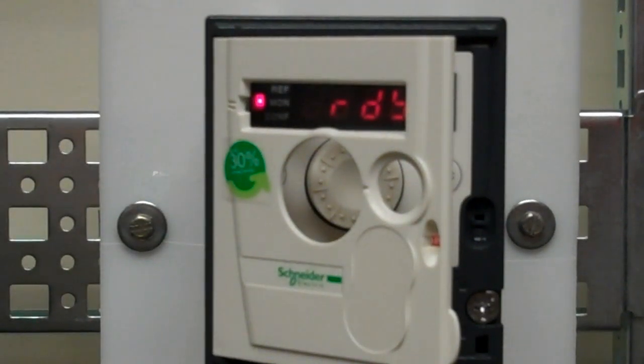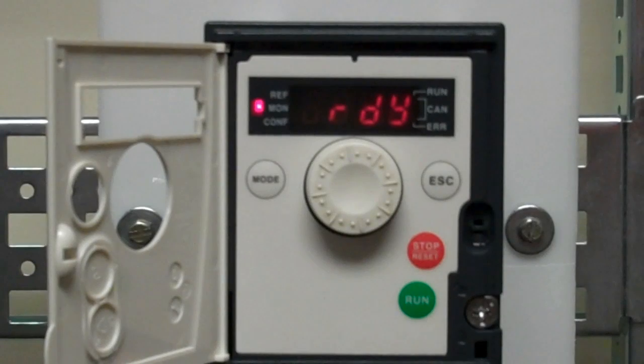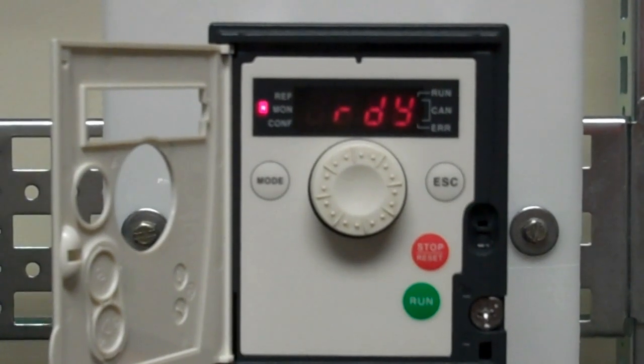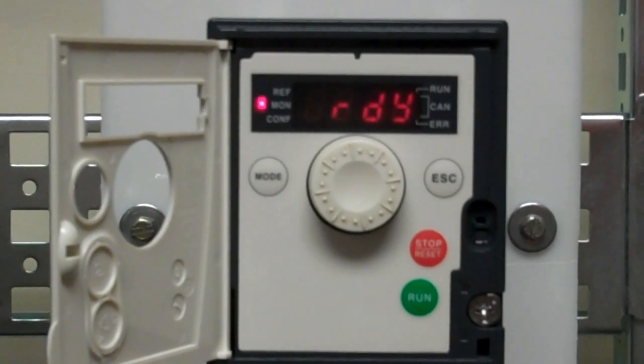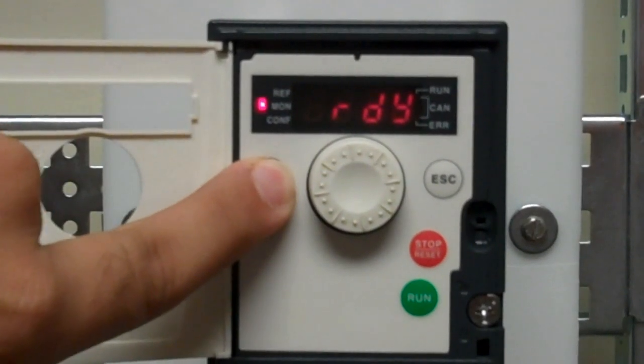The first thing we want to do is put the drive into local control first, and then change your run command to come from the terminals instead. Press the mode key and hold it for about three seconds to put the drive into local control.